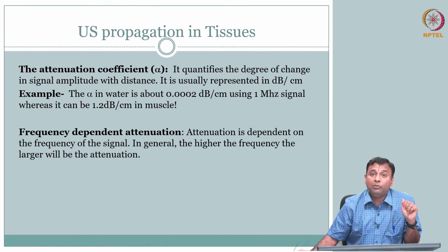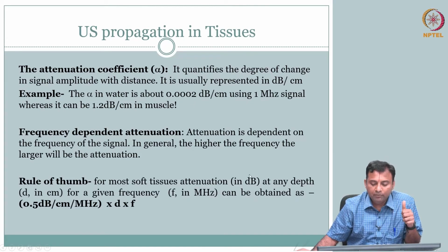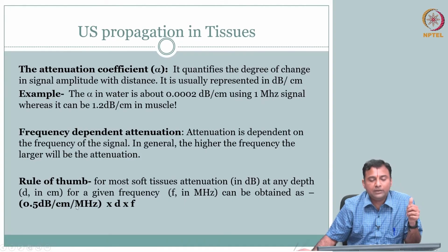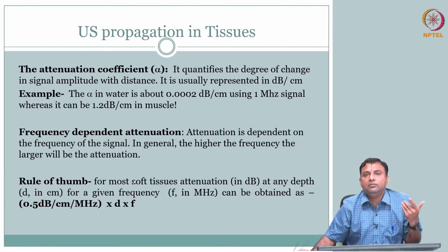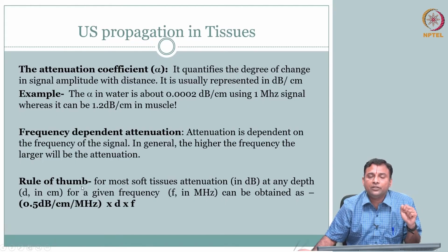Okay, better will be your resolution. Okay, so rule of thumb, for most soft tissue, you can get about half a dB per centimeter per megahertz.